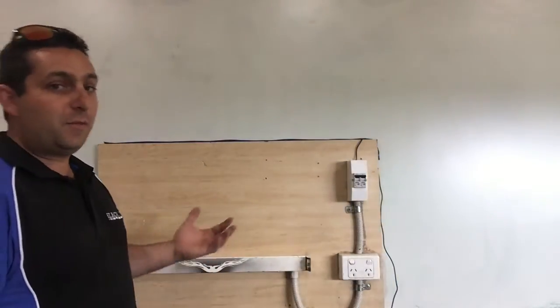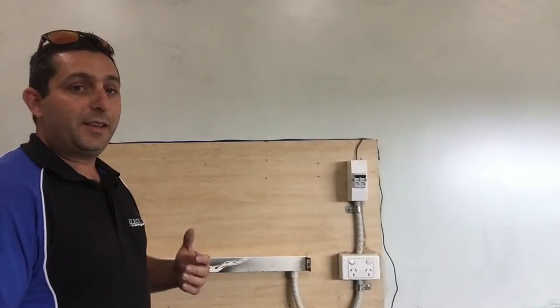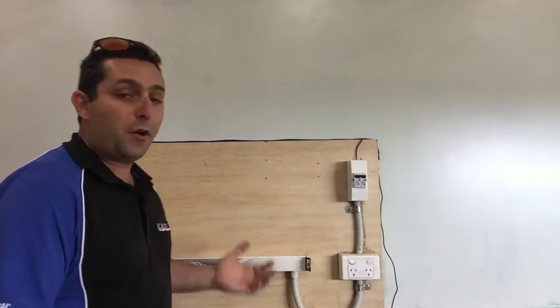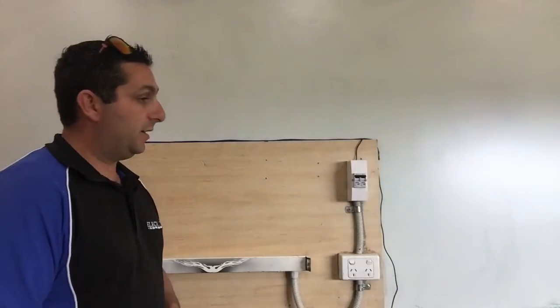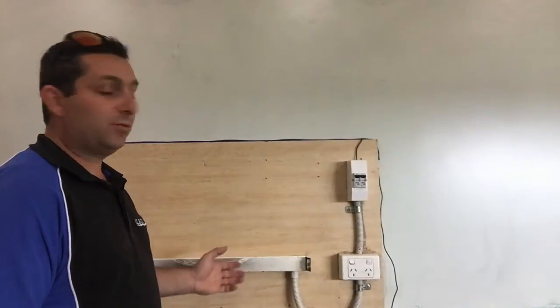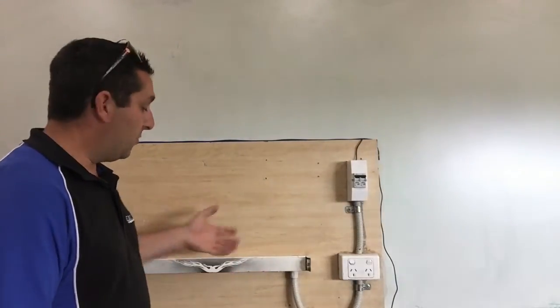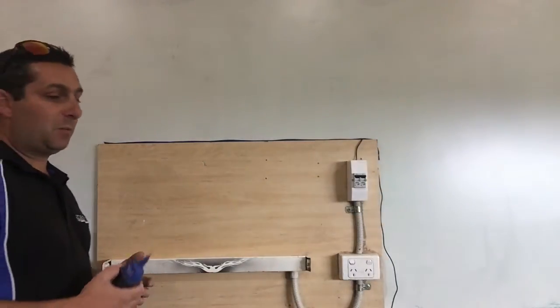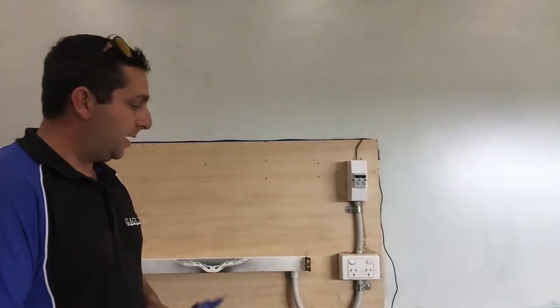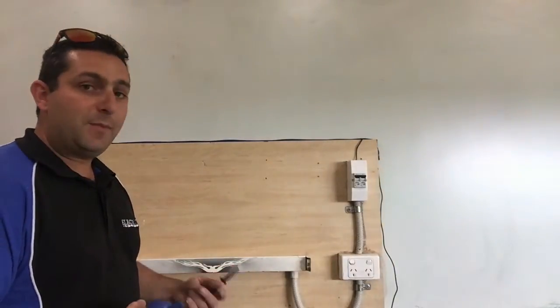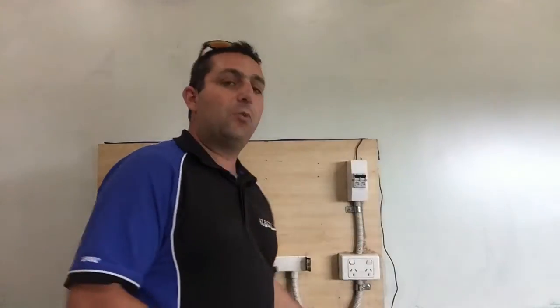There's an important thing first up. You need to understand you've been called to a job where there's a fault, and along with that there may be the potential to be stray voltages. We don't want to go ahead and start touching anything before we establish whether there's any stray voltages or anything that can be harmful. When you get into your exam, you'll be given a known earth, so you'll be told where there's an earthing point, but in the real world you'd want to establish a trailing lead into a known earth. So you can establish that you can work safely.